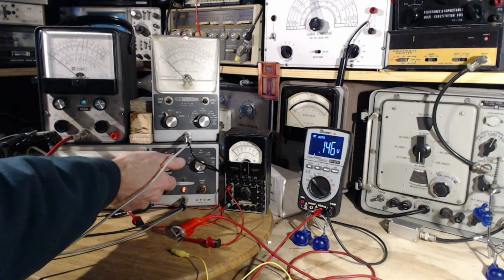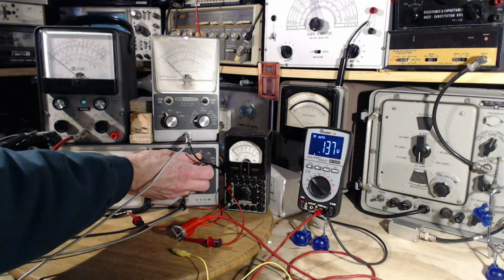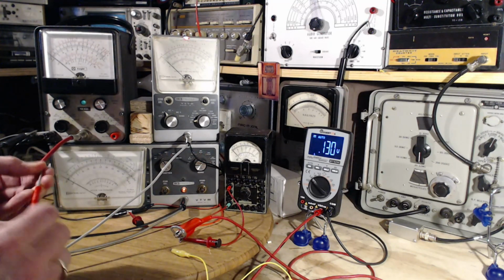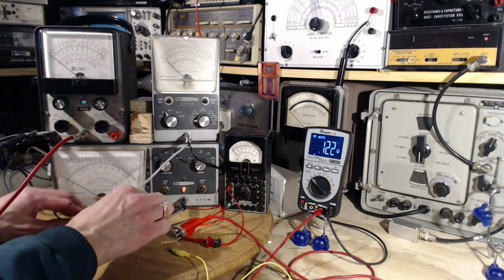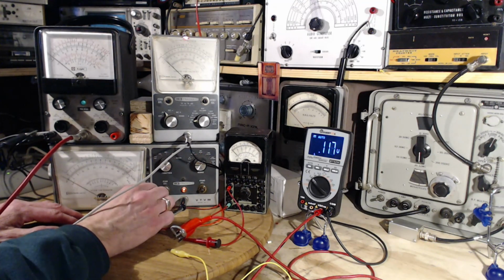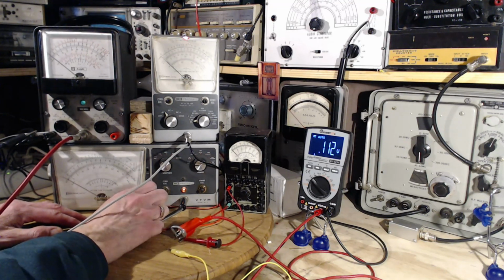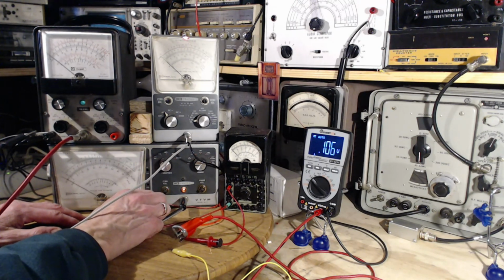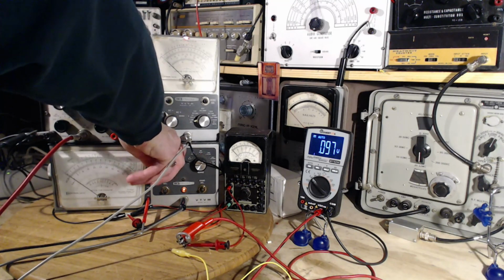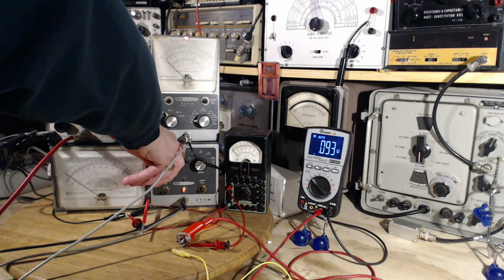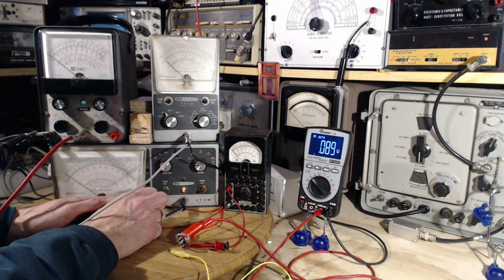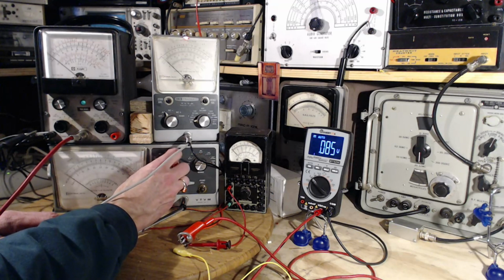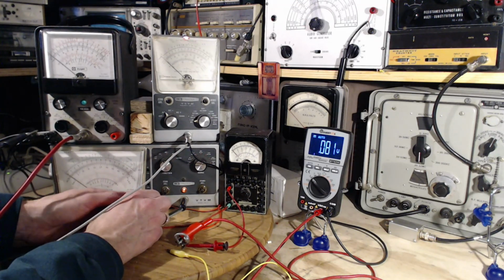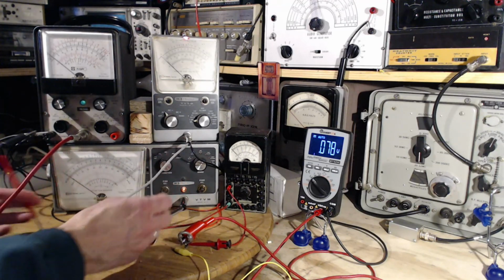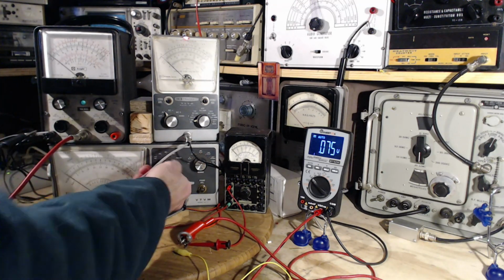Now the last one. Switch it to AC. Lowest voltage. I'm way down. AC balance. Okay, raise her up a bit. Hey, where are you? Whew, it's way off. There we are. Check the 3 positions now. It's a small movement there. I'm sure I'm within the accuracy of this meter. There we are. That's pretty good. No movement. It's sitting right on 0 too. Okay, so that function is done. They're all set to AC, most sensitive scale now.